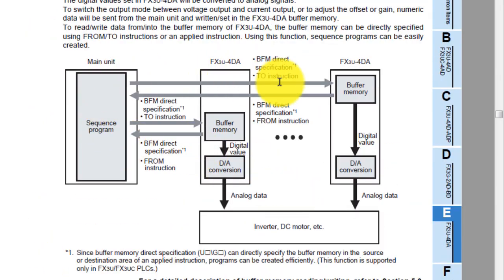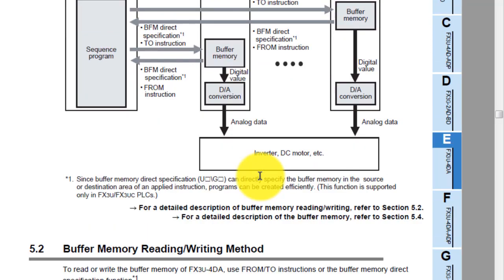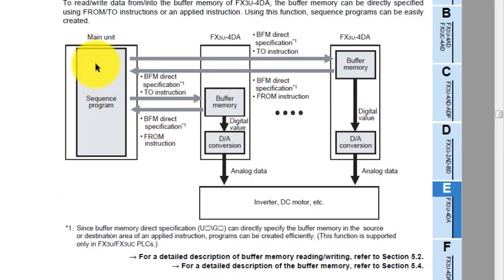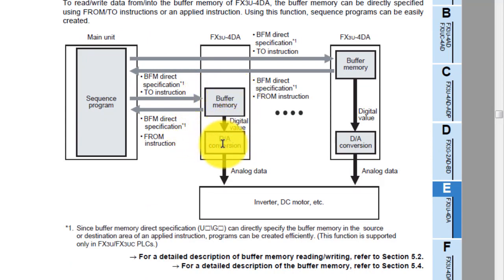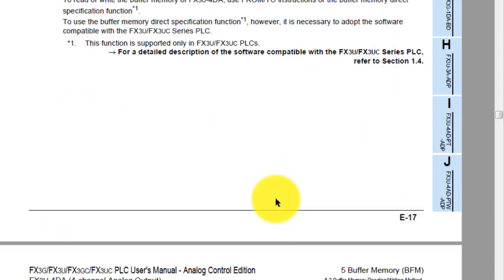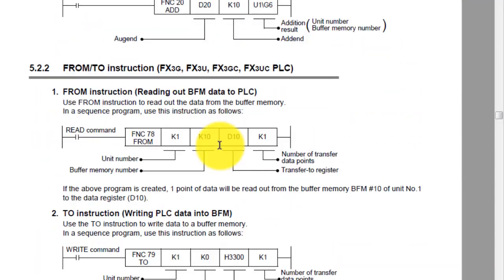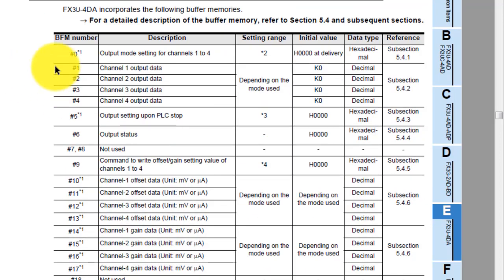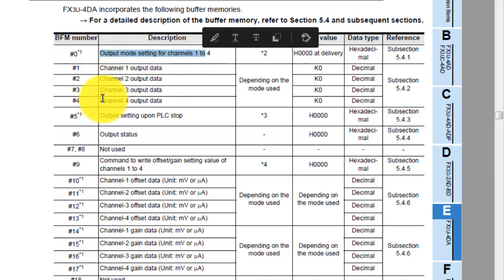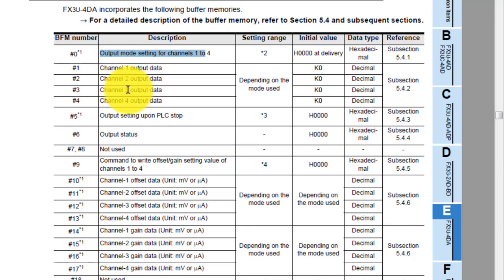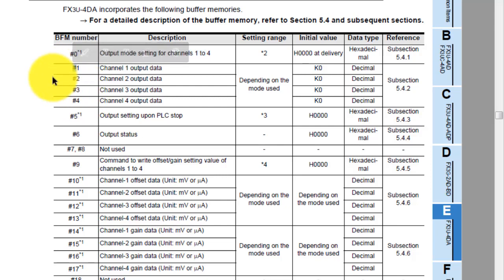This is the communication system between FX3U-4DA and the main PLC unit. Your PLC programming will send commands to the buffer memory. Buffer memory gives the command to the D/A conversion in the analog module, and this value goes out to the inverter or DC motor. Buffer memory number 0 is for output mode setting, and buffer memory locations 1 through 4 hold the output values for channels 1, 2, 3, and 4.